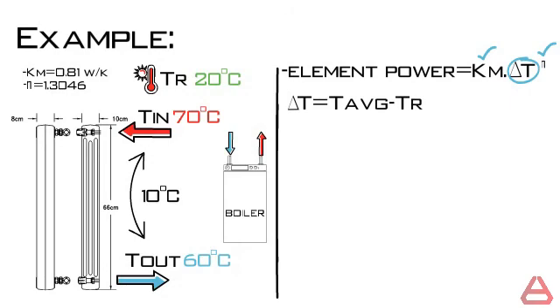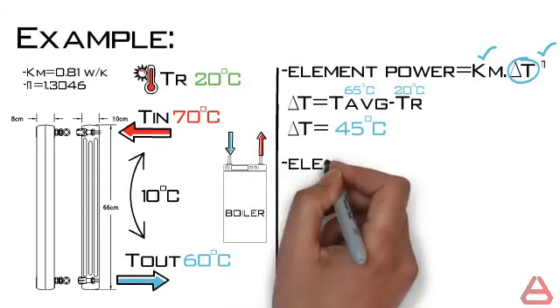So the average radiator temperature would be the average of 70 and 60 and that is equal to 65 degrees Celsius. Therefore delta T would be 65 minus 20 which is equal to 45 degrees Celsius.